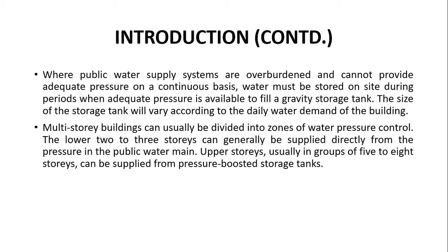The lower two to three stories can generally be supplied water directly from the public water main because the pressure is strong enough — up to a maximum of three stories. For upper stories, we group them in five to eight stories, and each group is provided by a pressure-boosted storage tank. A specific pressure pump boosts the pressure and takes water from the third story up to the next eight stories and stores it in a storage tank. Then that storage tank is connected to another pressure booster pump to carry water to the next eight stories, and that is how the system works.